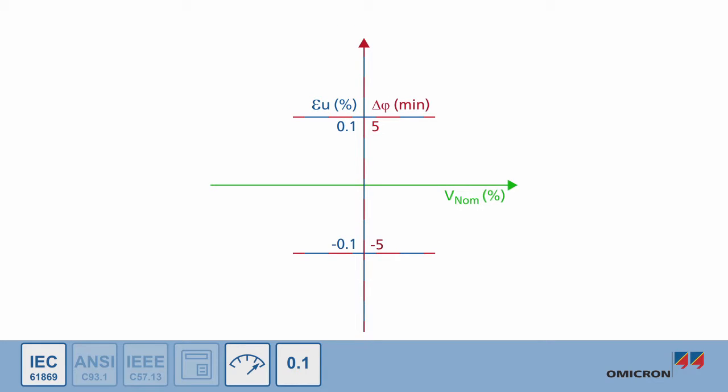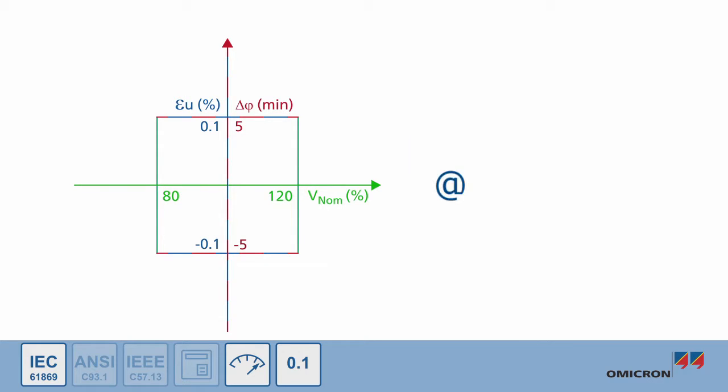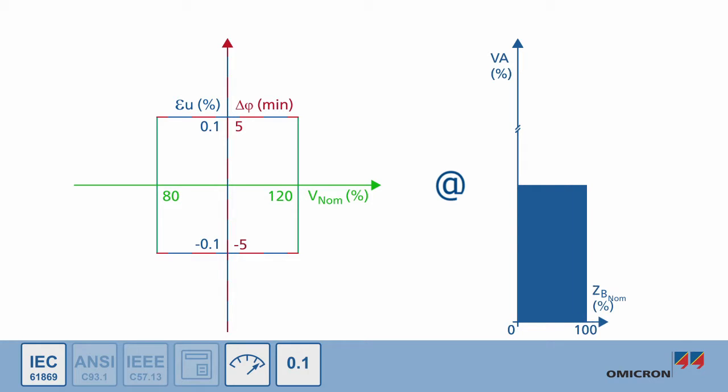The voltage transformer must maintain this high level of precision for primary voltages ranging from 80 to 120% of its nominal voltage. This performance must be maintained for all burdens ranging from 0 to 100% of the nominal burden for unity power factor for burdens below 10VA. For burdens above 10VA, the voltage transformer must be able to maintain this accuracy for burdens ranging from 25 to 100% of its nominal burden at a lagging power factor of 0.8.